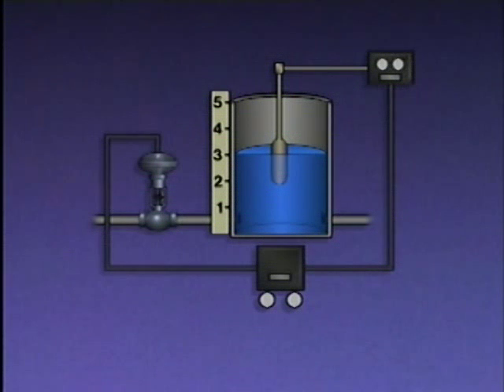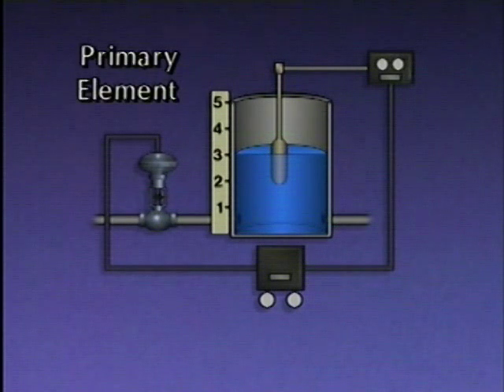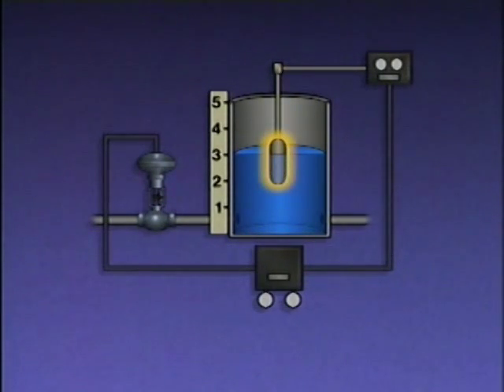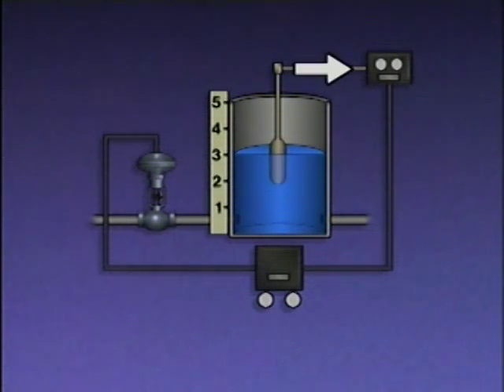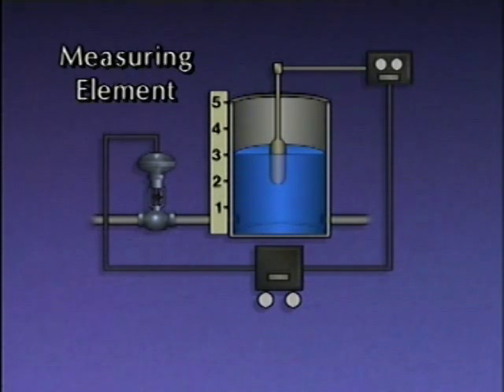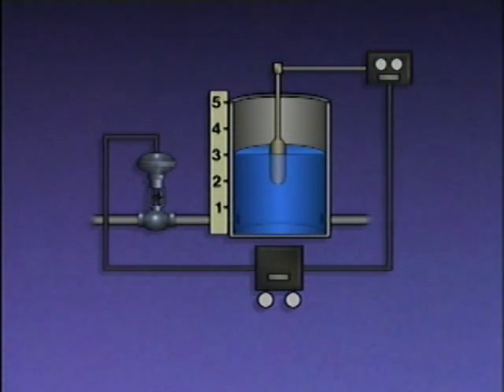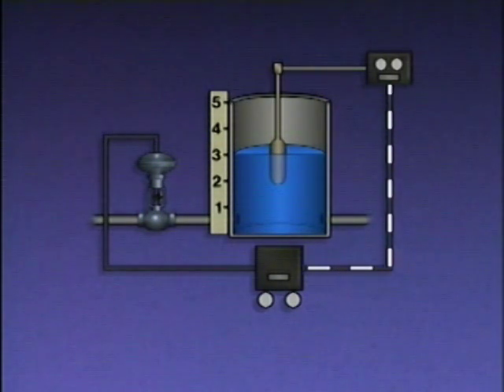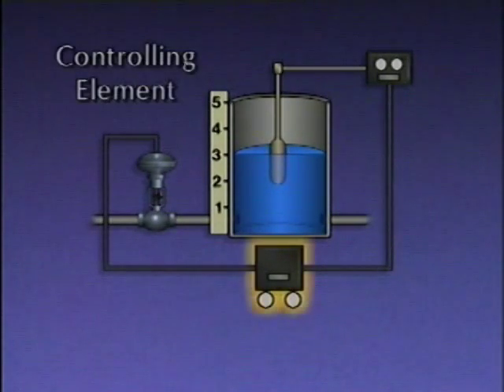As with all automatic control systems, this system has four basic parts, or elements. One element, the primary element, is a sensing device that's located where the process variable is monitored. In this system, the primary element is a float that senses the level of water in the tank. The float is connected through a mechanical linkage to the second element in the system, a measuring element. In this system, the measuring element is a transmitter. The transmitter detects the position of the float and transmits a signal representing the level in the tank to the third element in the system, a controlling element.